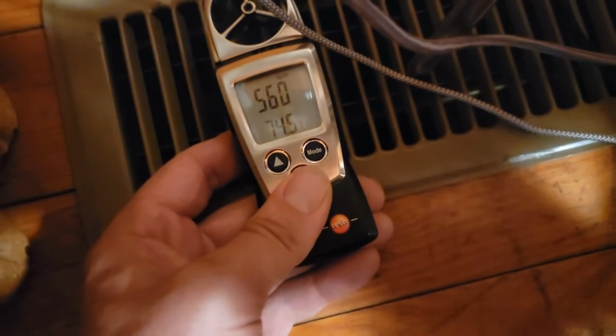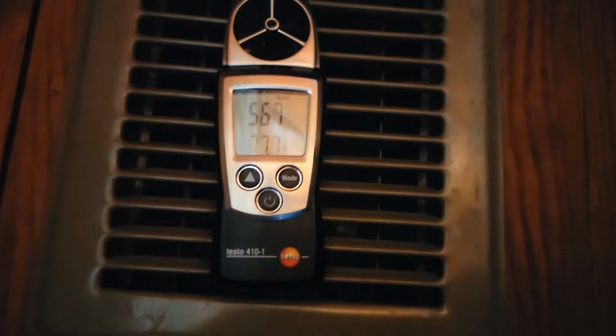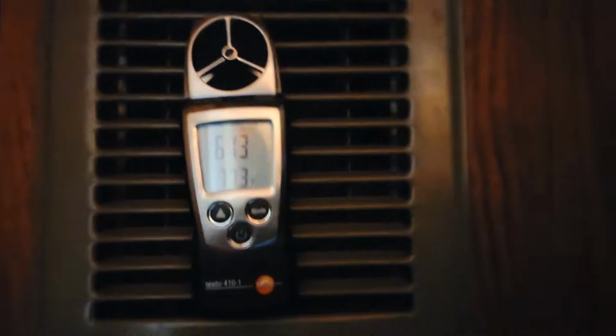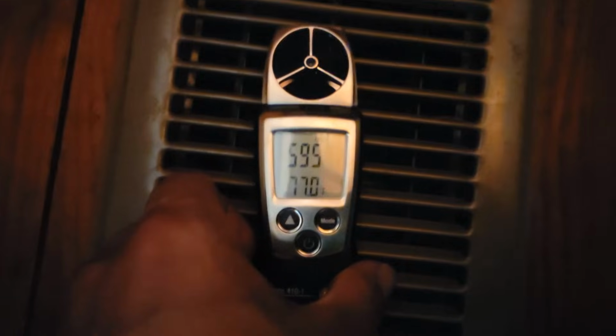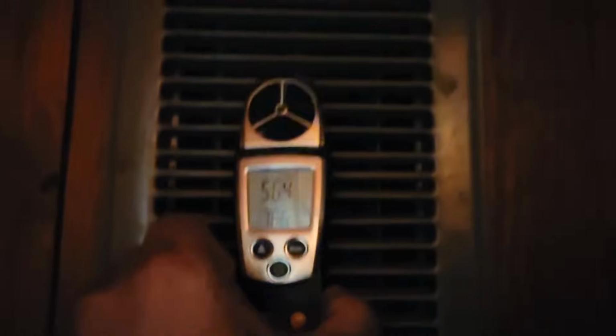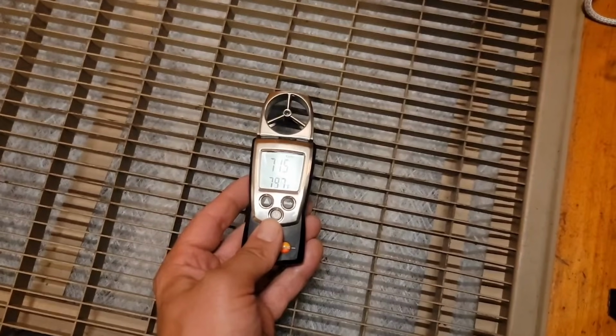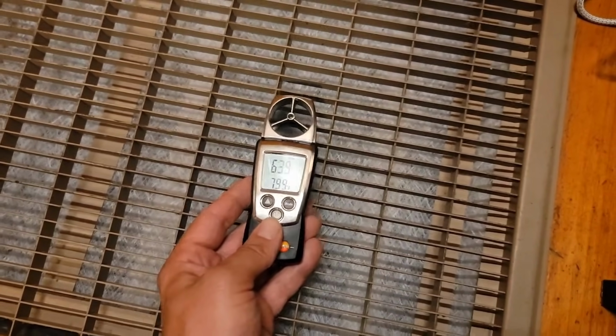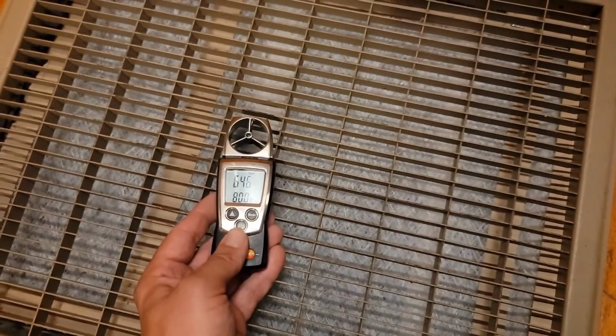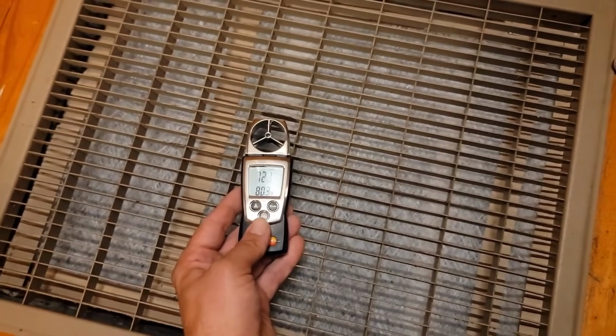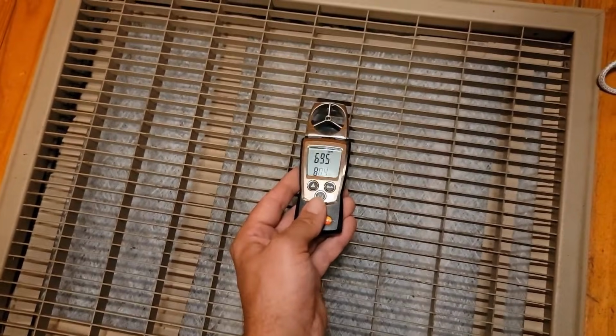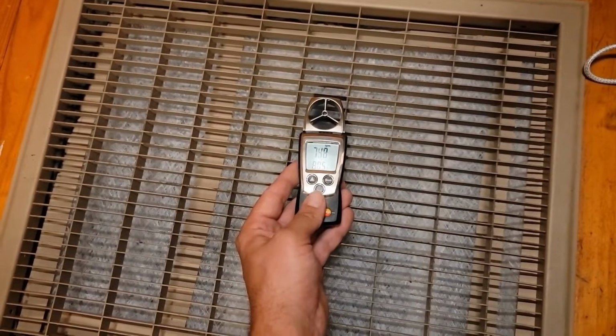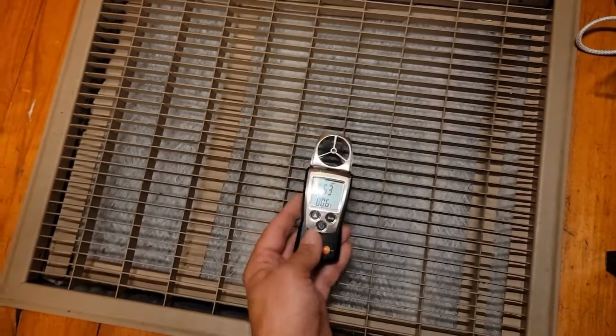This one's doing about 550. Vent for the bedroom, it is blowing 600 feet per minute. So, awesome. All right, let's see what it's pulling. About 700. Wow, you usually don't want to see more than 500, so it's really pushing some air. In this case, pulling air.